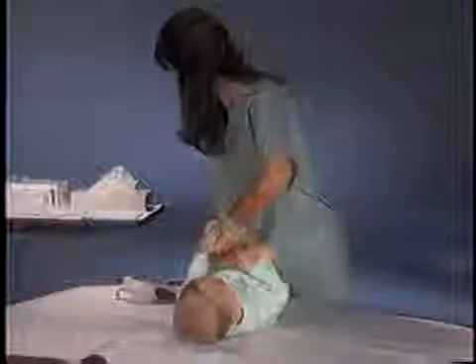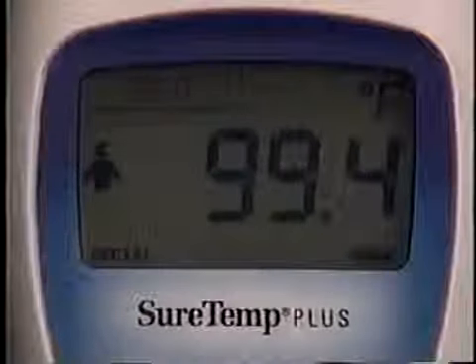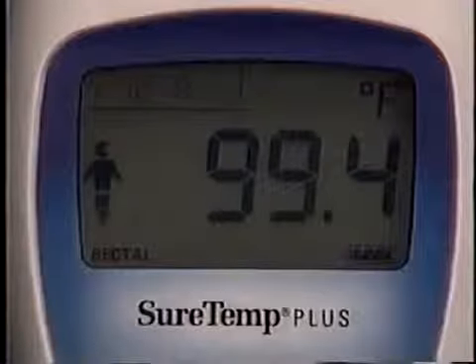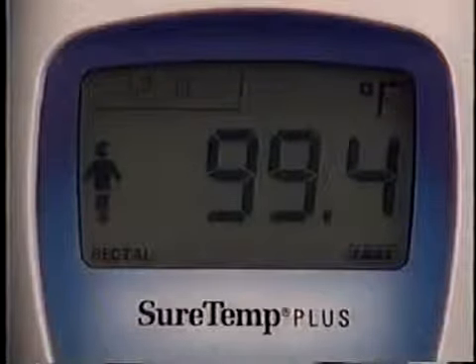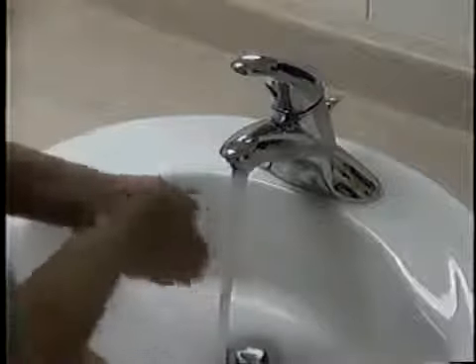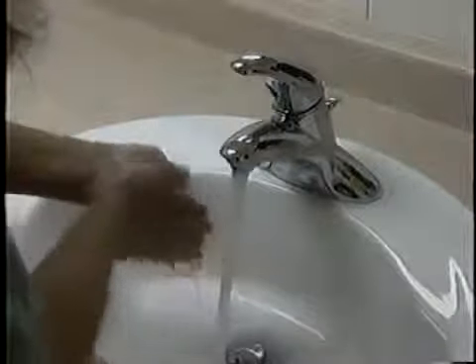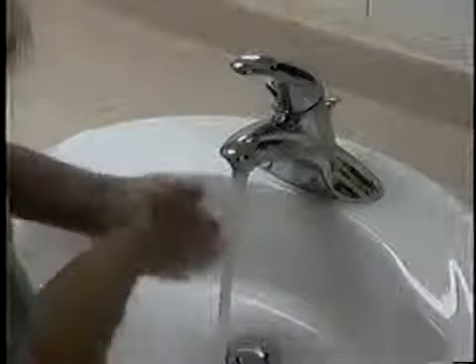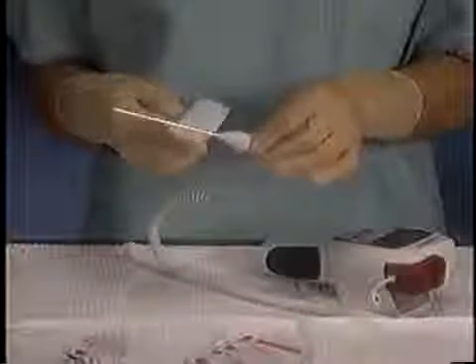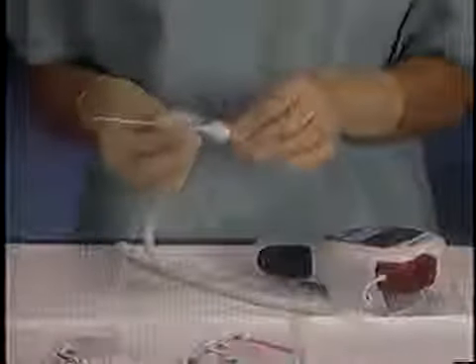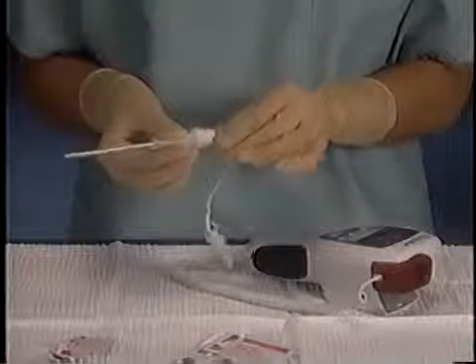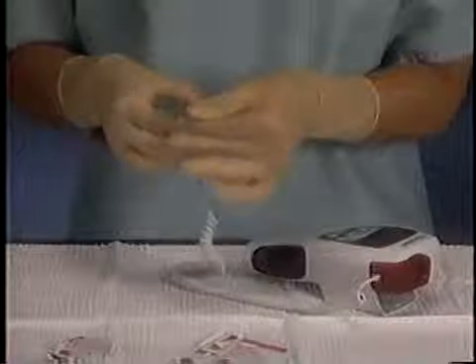Remove the probe from the patient's rectum and eject the probe cover. Note the temperature, which remains on the display for 30 seconds, or until you place the probe back in the well. Be sure to wash your hands after taking a rectal temperature to reduce the risk of cross-contamination and nosocomial infection. If contamination occurs, wipe down the thermometer, probe, and probe cord with an approved disinfectant. If you suspect that the probe well is contaminated, remove it and then disinfect or replace it.